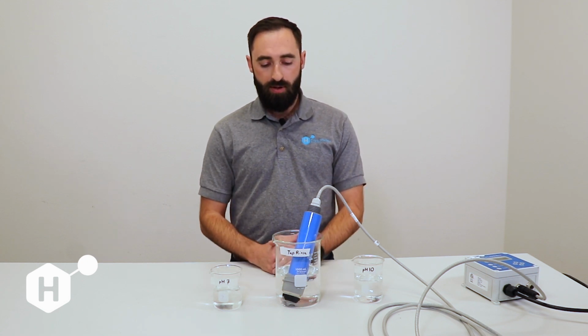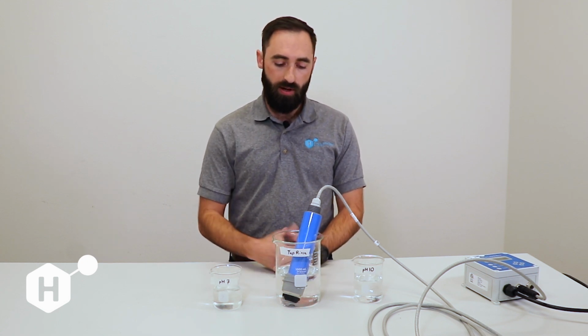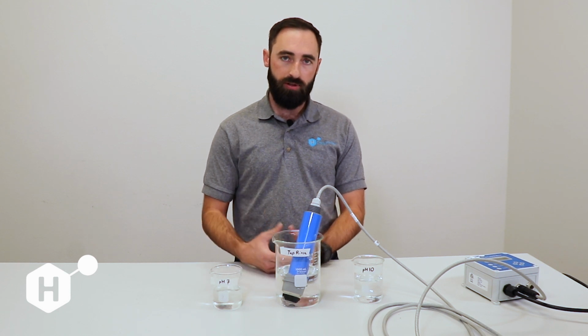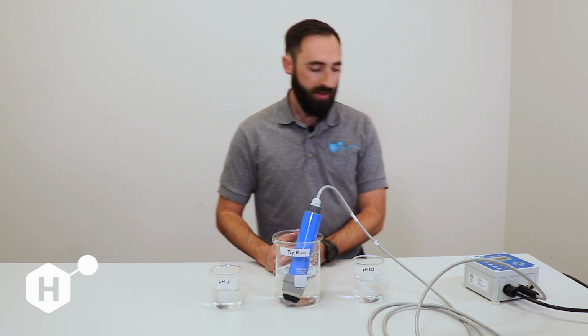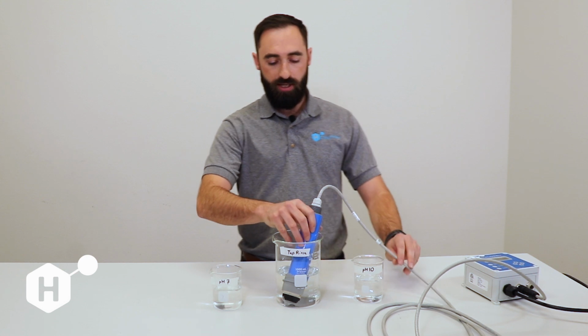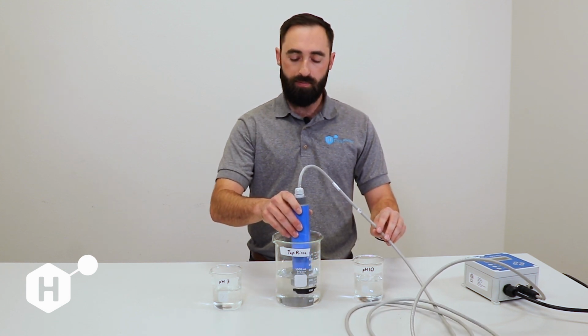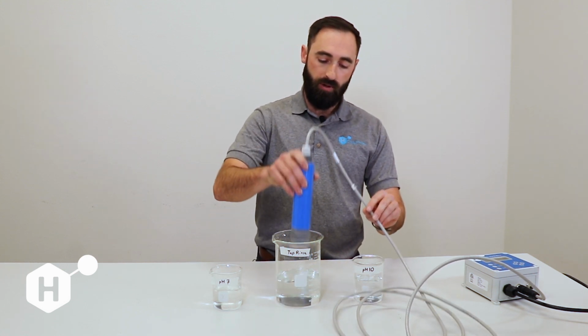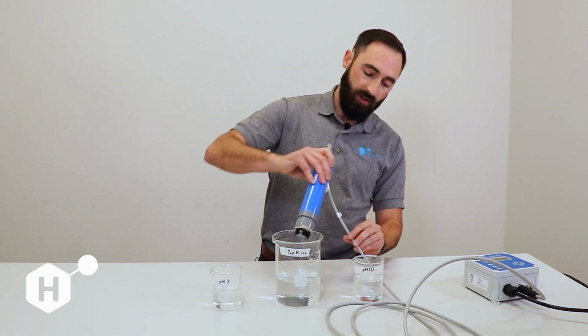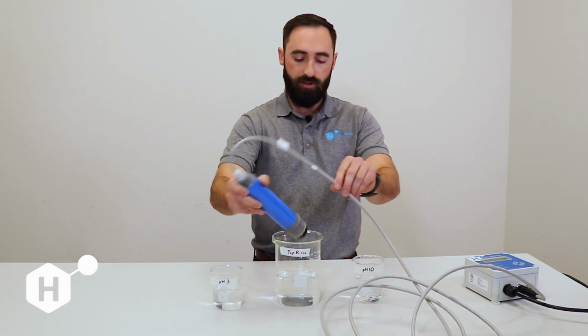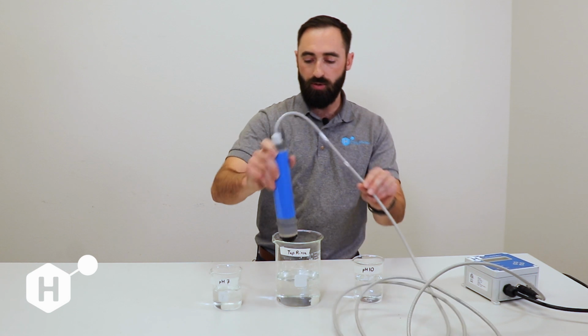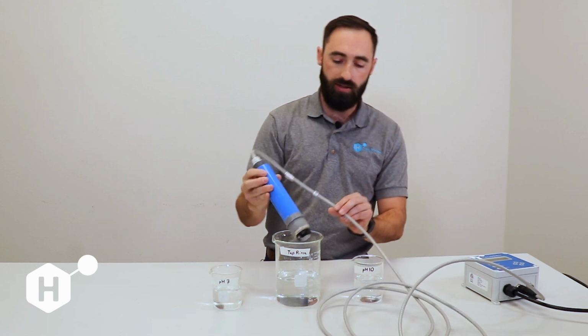So, as you can see, my sensor is already running and adequately primed just in the tap water, so we know everything's working correctly. So the first thing we're going to do is go ahead and move into our pH 7 buffer. We're going to pull it out of the tap water. You're going to want to get rid of as much water as you can. That way we're not degrading our pH 7 solution here.